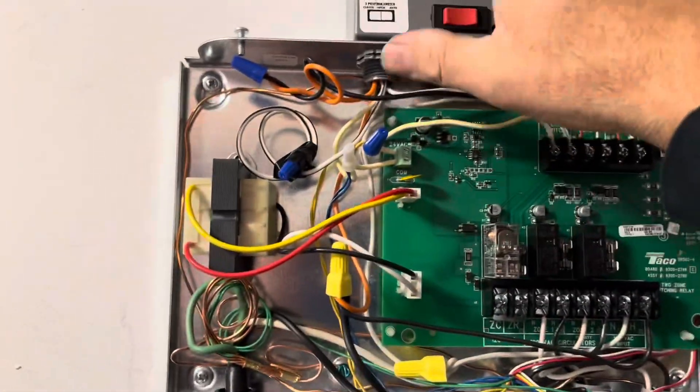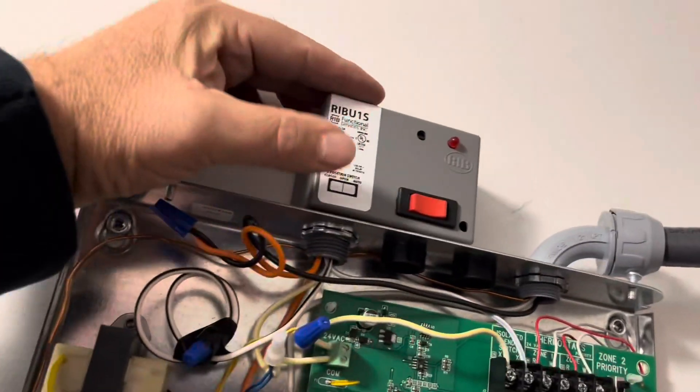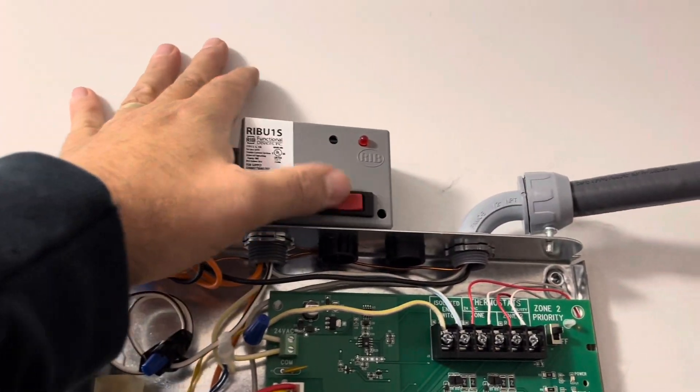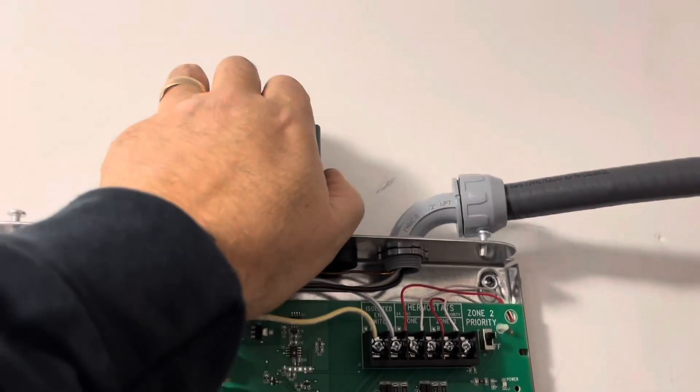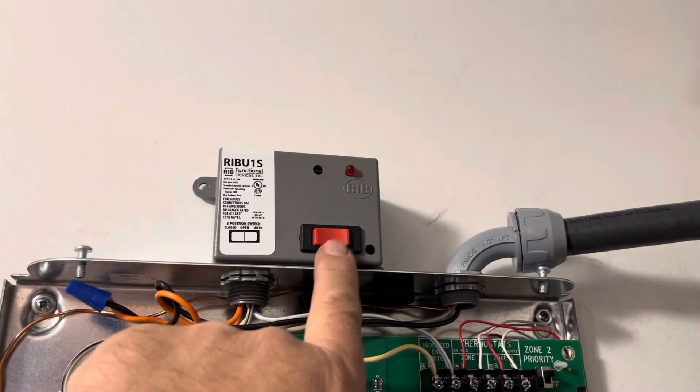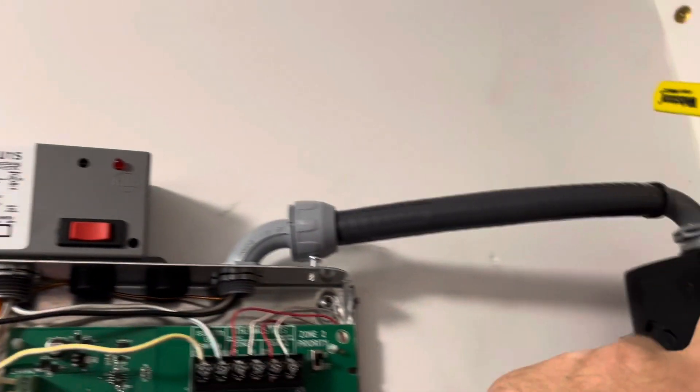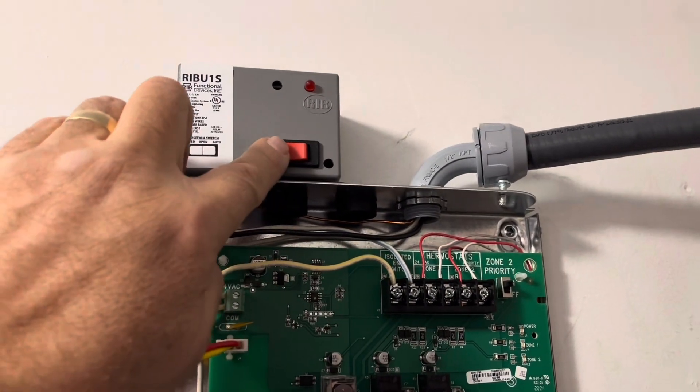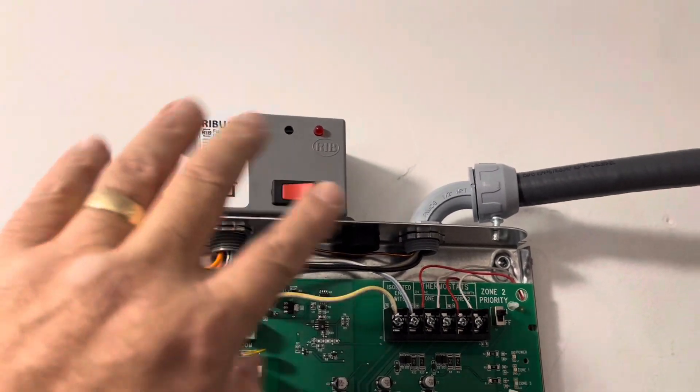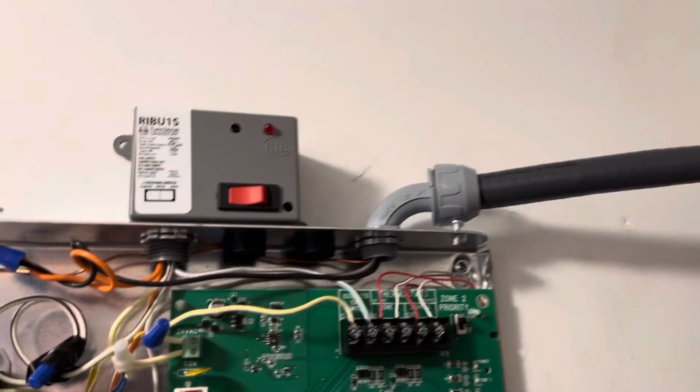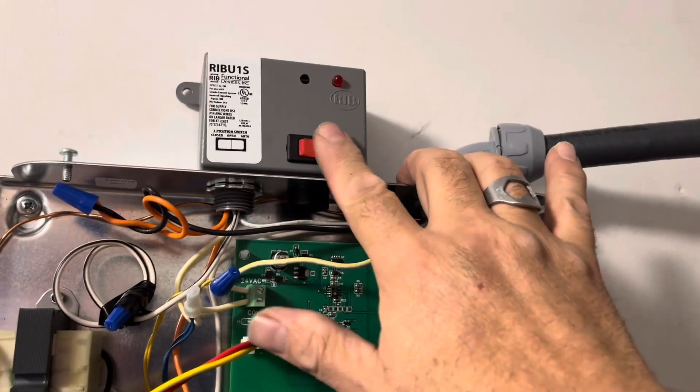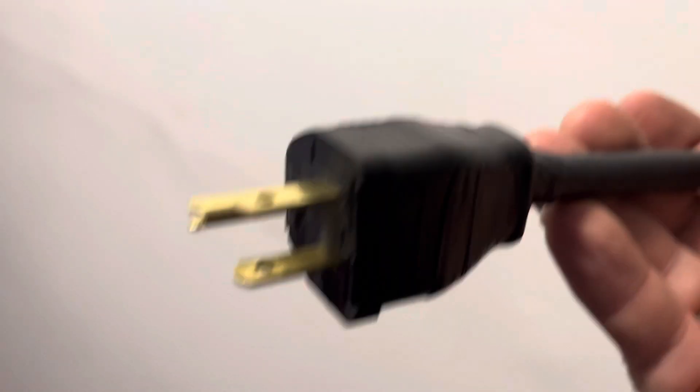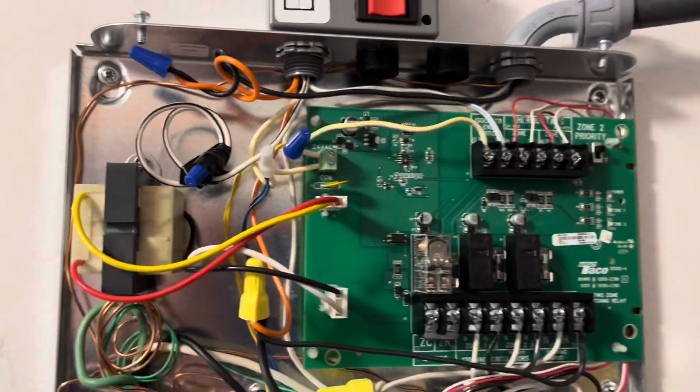And then because the primary is a special one, this is a special three-way switch. The middle position allows this motor to be controlled by this circuit board. If I turn it to here, this motor will never go on. And if I turn it to here, this motor is forced on. It's not turning on right now because it's not plugged in and it's not plugged in because there's no water in the system.